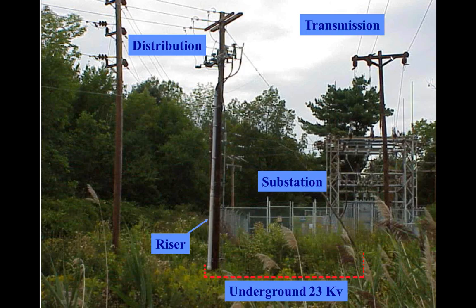Now, a substation. Here's where all the fun starts. Here we got a transmission feed coming in, drops into the substation. The substation equipment steps it down from transmission voltage to distribution voltage. In this case, we're bringing it underground, and we're bringing it up the side of a pole, and this is the beginning of a uniquely numbered, uniquely named circuit that's going to go out and feed thousands of customers, but it originated at the substation.